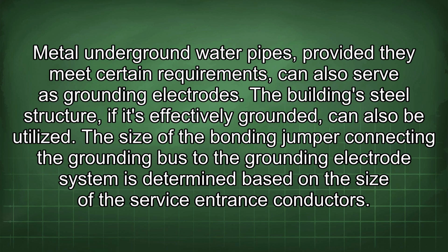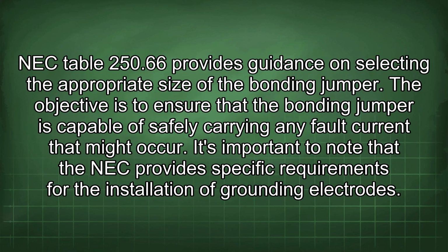The size of the bonding jumper connecting the grounding bus to the grounding electrode system is determined based on the size of the service entrance conductor. NEC Table 250.66 provides guidance on selecting the appropriate size of the bonding jumper. The objective is to ensure that the bonding jumper is capable of safely carrying any fault current that might occur.